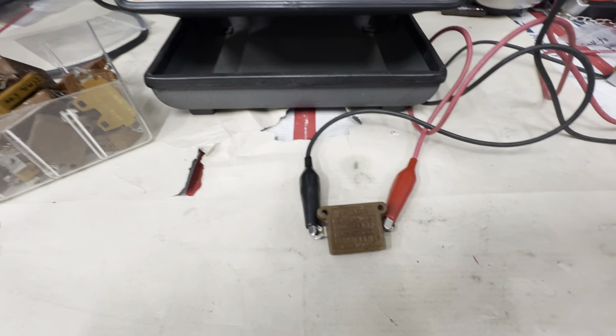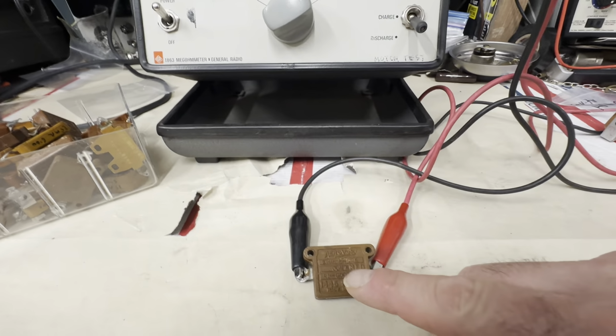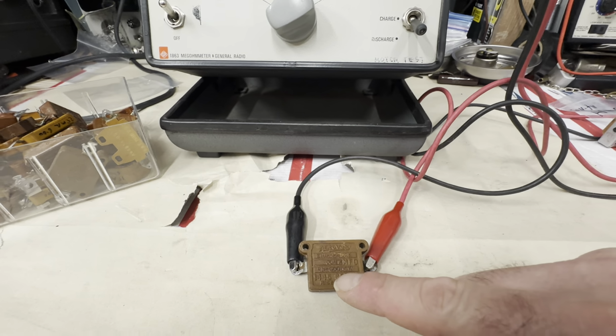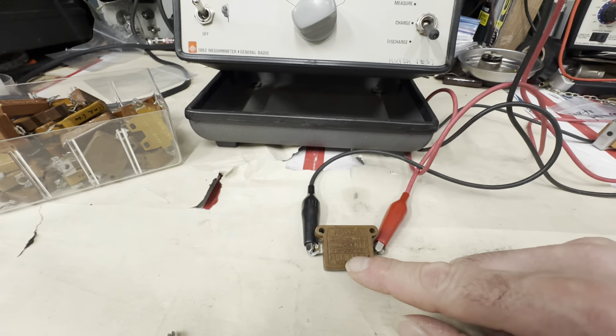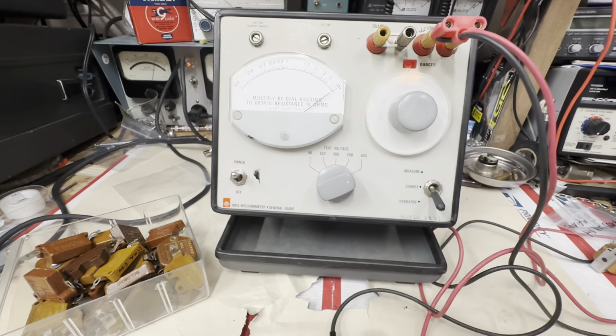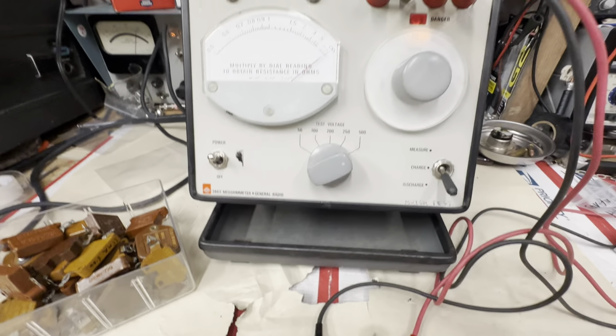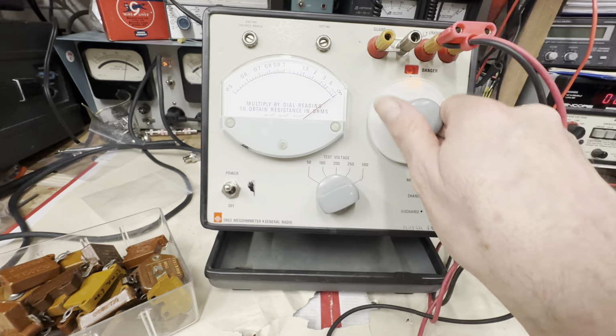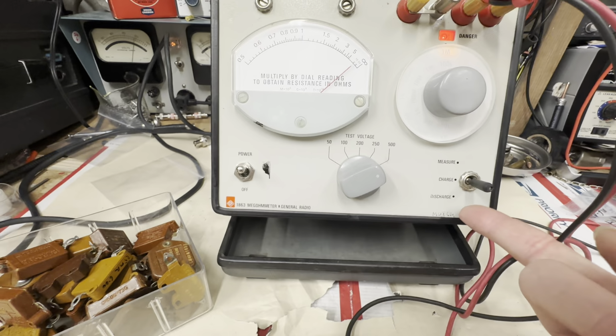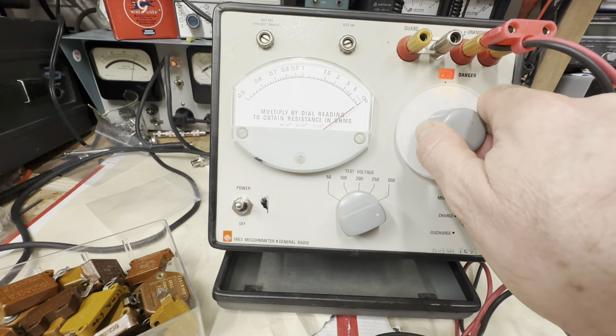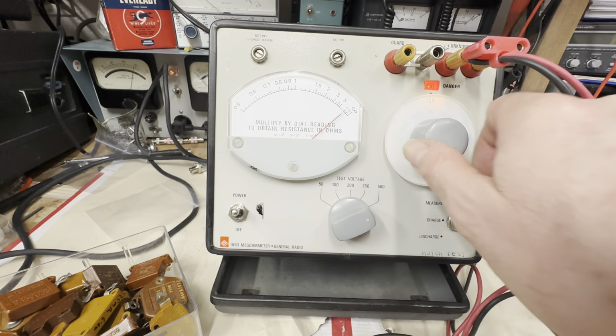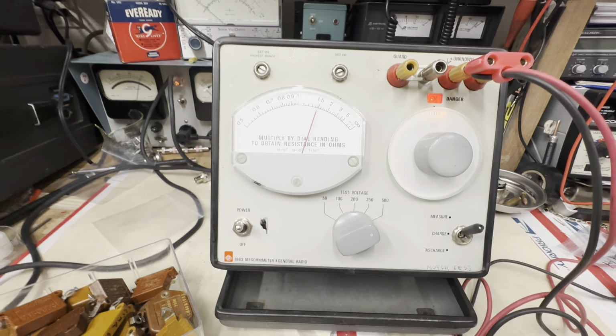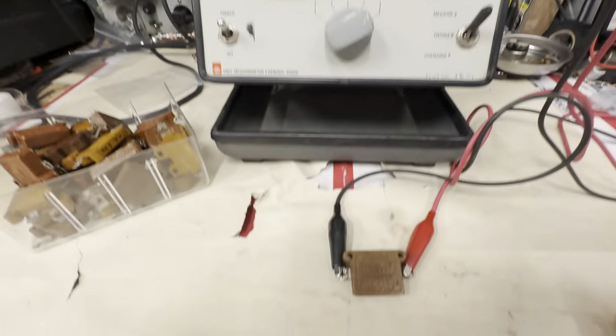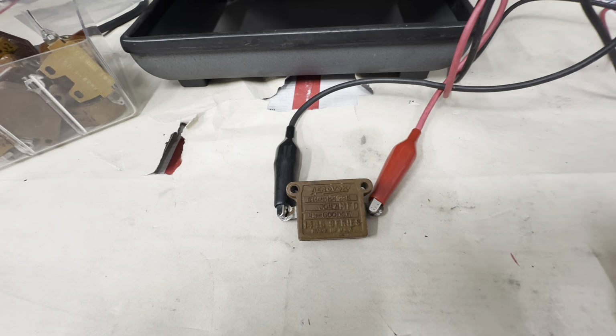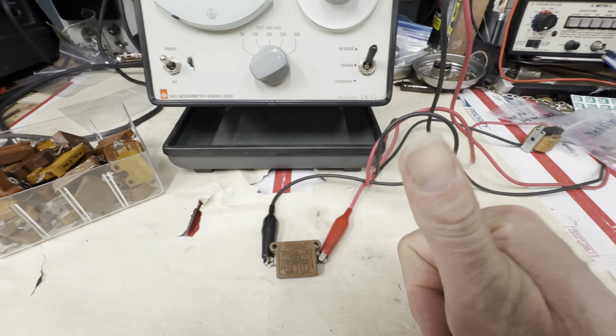We'll do one more. Okay, this is an Aerovox cap. Again, same genre, World War II, 0.0047 microfarads. And it looks like this one here is only a 600 volt DC, so we're going to put 500 volts DC on it. So this is from a very low voltage transmitter. Okay, let me crank this back down to 1. Here we go. Okay, it's charged, and let's see what we get. Wow, 10 gig. That's 100 gig right there. It's at 150 gigs right now, so essentially there is 0 leakage out of this guy. This one's a definite thumbs up. We got another winner.